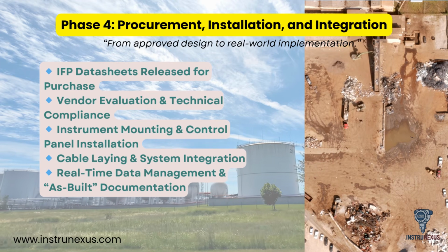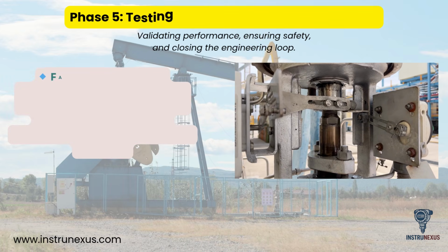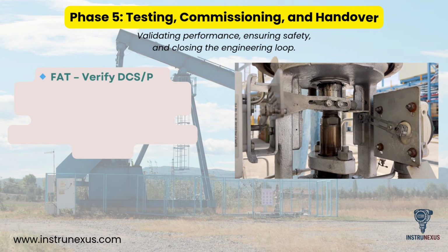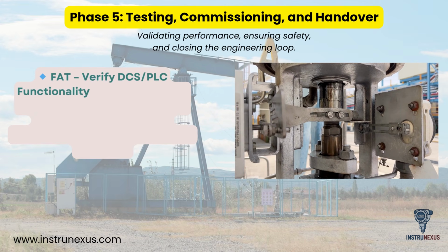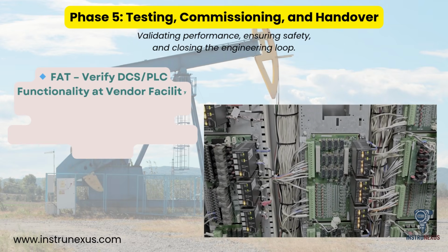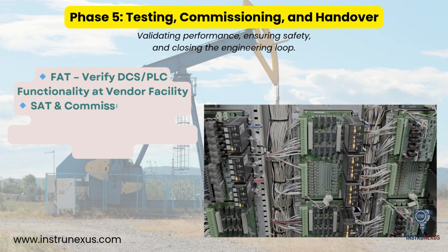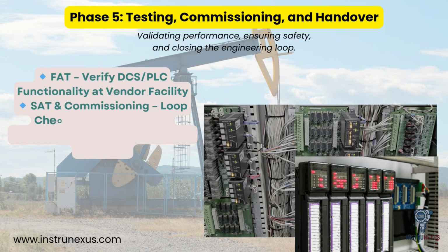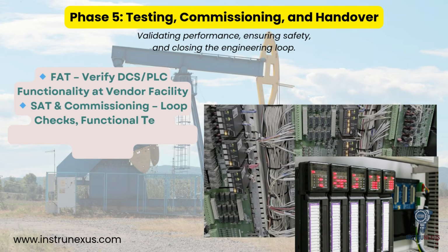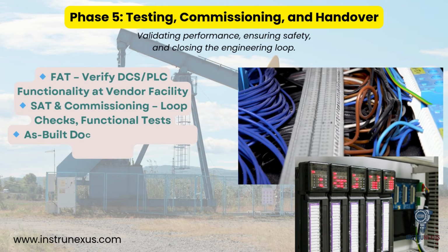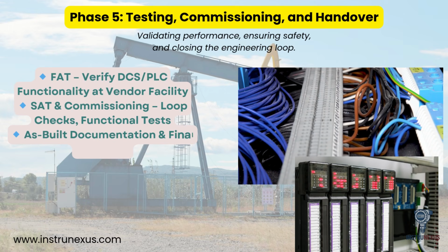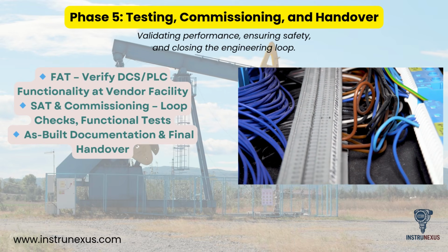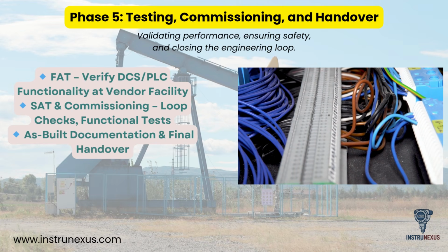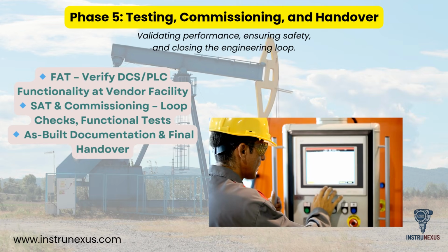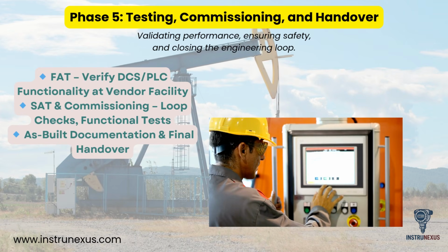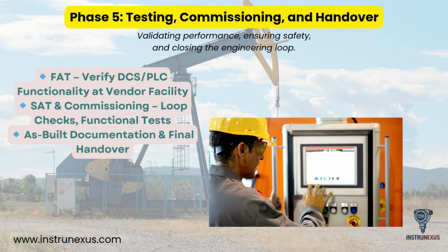Where engineering meets operation, the testing, commissioning, and handover phase validates the functionality, performance, and safety of the installed control and instrumentation system. It begins with the Factory Acceptance Test, or FAT, conducted at the vendor's facility to verify the DCS or PLC configuration against the finalized control narratives and design specifications. A clear and detailed control narrative is crucial. It eliminates programming ambiguity and ensures an efficient, accurate validation of the configured logic.